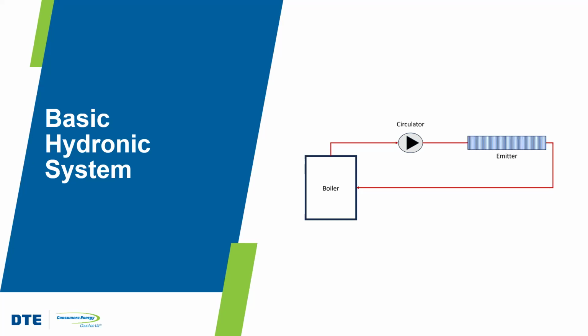Usually that delta T is about 20 degrees is generally what we design for, but that's kind of an old rule of thumb, and we can actually go with a higher delta T across that boiler, and that would improve the efficiency of our system. It might even allow us to install smaller piping as well, which would reduce costs, right?